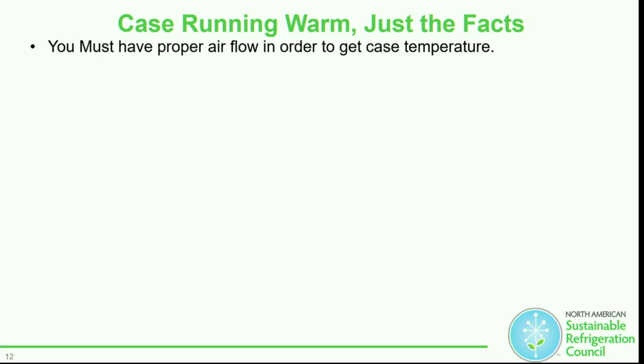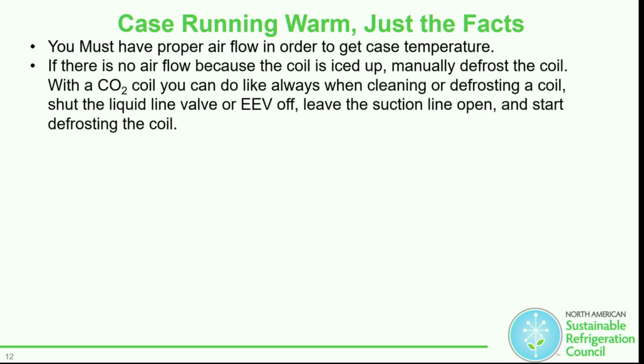Once again, you must have the proper airflow in order to get the case temperature. If there is no airflow because the coil is iced up, when manually defrosting a coil, I would recommend looking at the coil to see what the frost pattern looks like. It might give you some hints of what's actually going on. For example, if you have a system with B15 here and B14 here, they might not be going into defrost at the same time. If you don't have a divider between those cases, humid hot air is going to go into one side and keep going, and each one of those sides is not going to fully defrost.